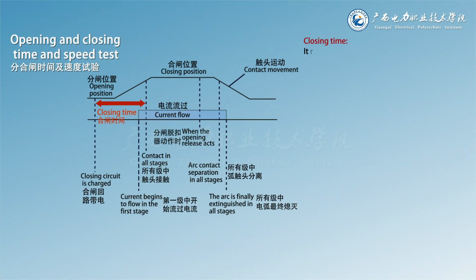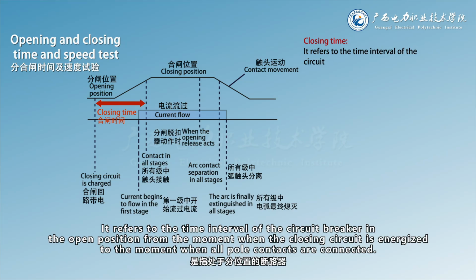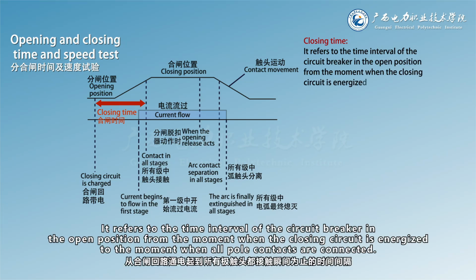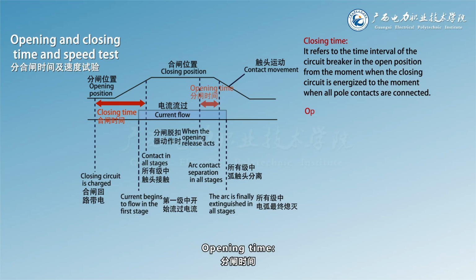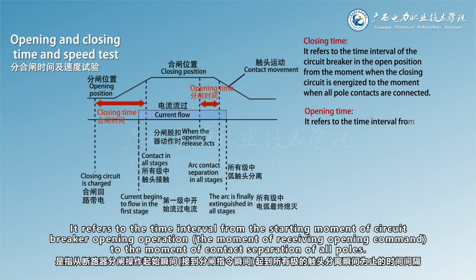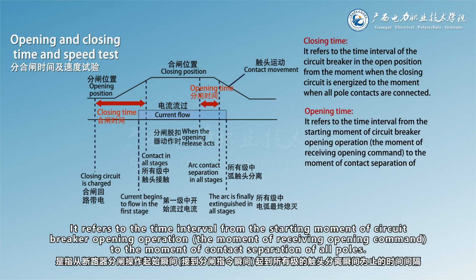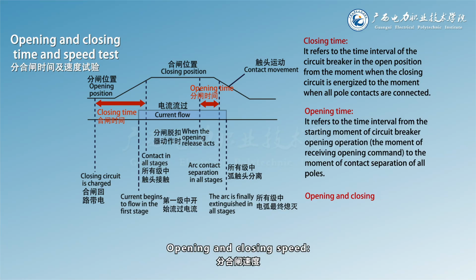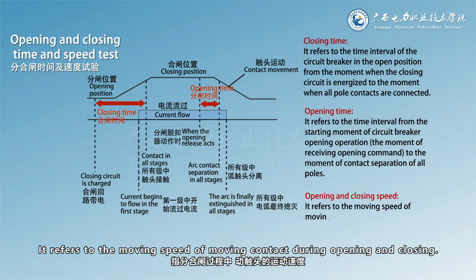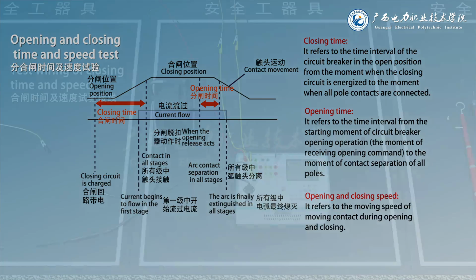Closing time. It refers to the time interval of the circuit breaker in the open position from the moment when the closing circuit is energized to the moment when all pole contacts are connected. Opening time. It refers to the time interval from the starting moment of circuit breaker opening operation to the moment of contact separation of all poles. Opening and closing speed. It refers to the moving speed of moving contact during opening and closing.